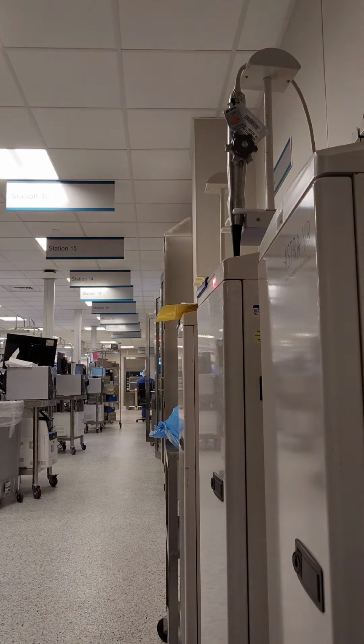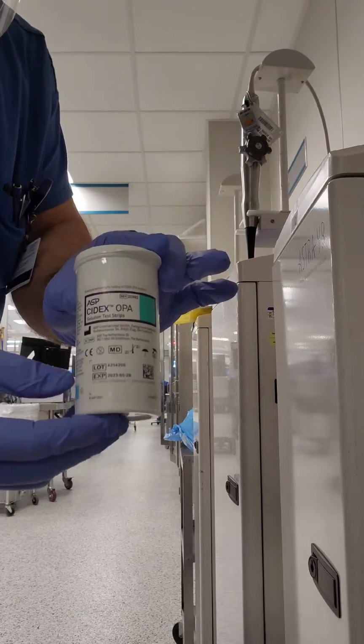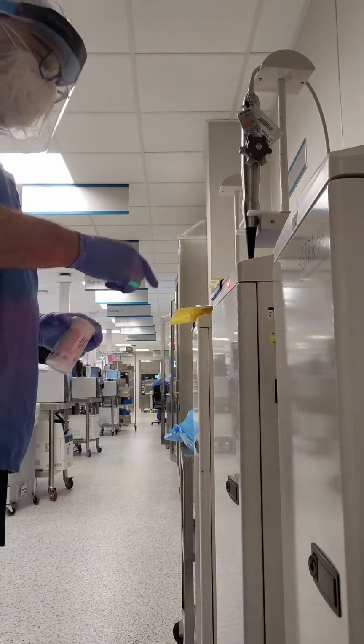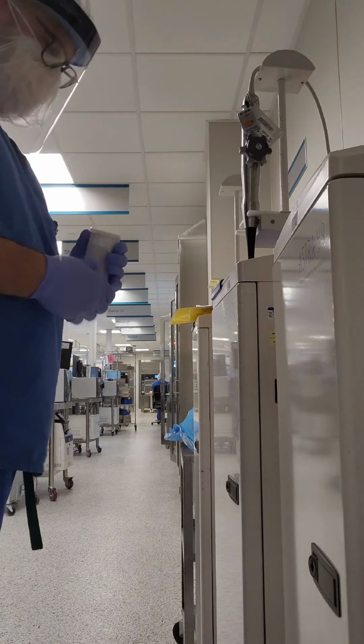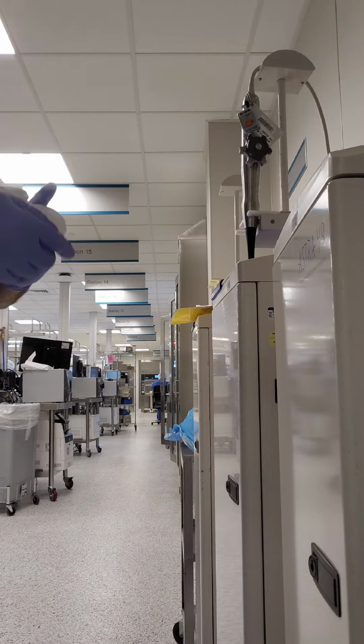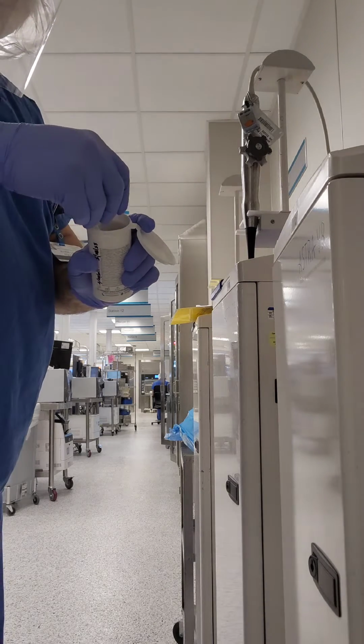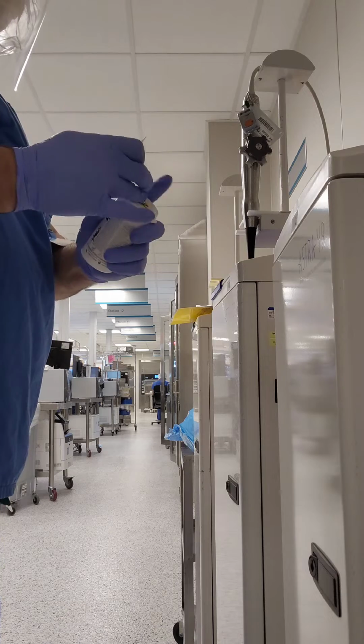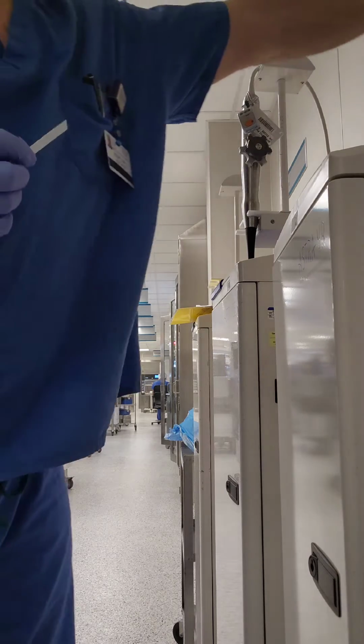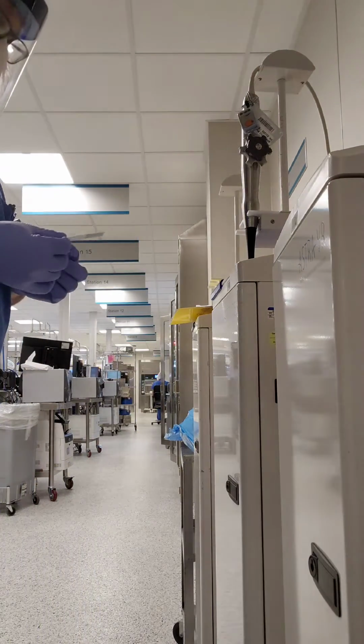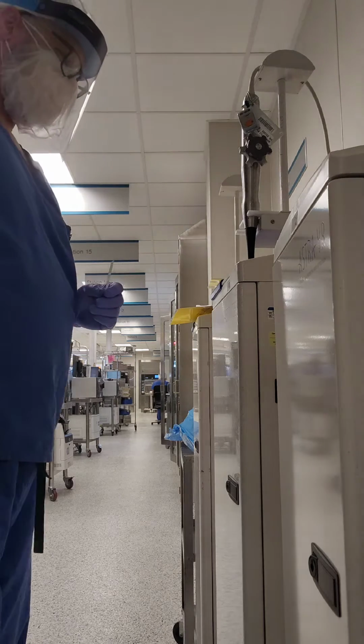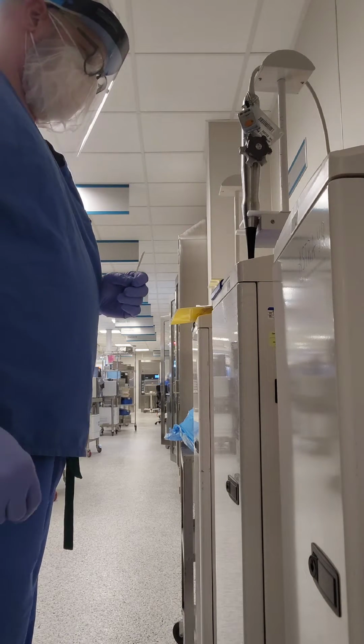The next thing it's going to ask for is the test strip, for the minimum effective concentration, or minimum recommended concentration, whichever one you want to call it. You want to go ahead and grab a strip out of there. Be careful not to touch the part that dips into the high-level disinfectant, and close the lid immediately.